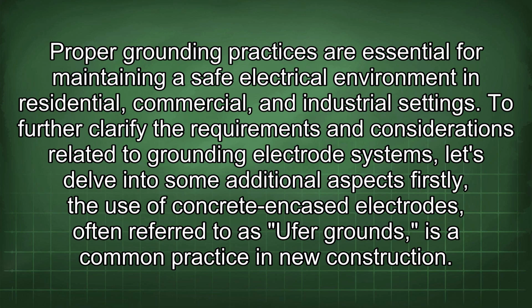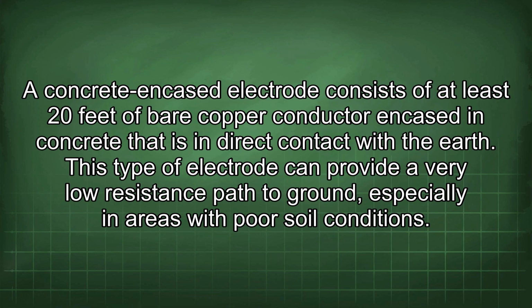To further clarify the requirements and considerations related to grounding electrode systems, let's delve into some additional aspects. Firstly, the use of concrete encased electrodes, often referred to as UFER grounds, is a common practice in new construction. A concrete encased electrode consists of at least 20 feet of bare copper conductor encased in concrete that is in direct contact with the earth. This type of electrode can provide a very low resistance path to ground, especially in areas with poor soil conditions.